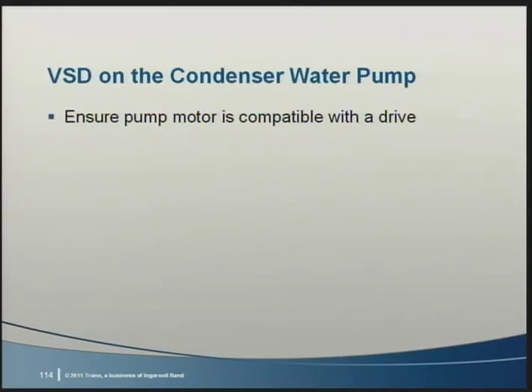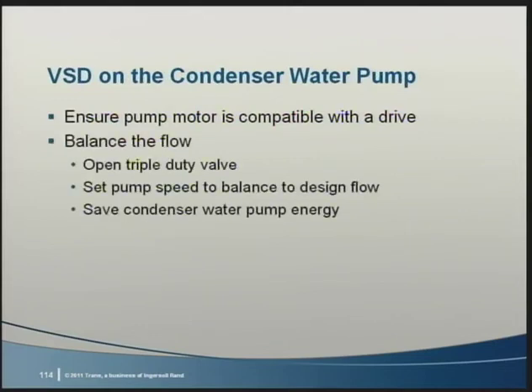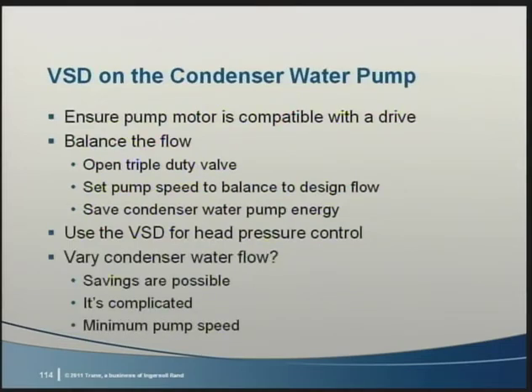Most condenser water systems have triple duty valves that balance the system, delivering the condenser water flow at full pump speed. One great reason to add a VSD to the condenser water pump is so that the balancing portion of the valve can be fully opened, the pump speed ramped down to give the design flow, and pump energy can be saved without affecting anything else. That will likely pay back in many applications. The VSD can also be used for head pressure control. The next question is, should we vary the flow rate during system operation?